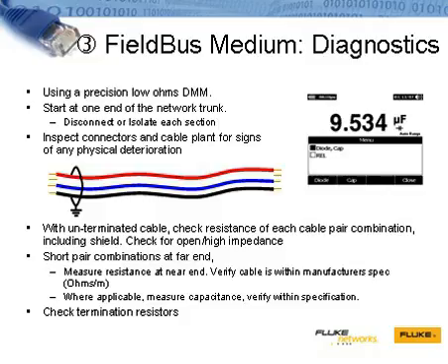Often in industrial field buses, we use standard common electrical AWG grade 2, 4, or 8 pair cables. These are untwisted or twisted cables with no set of special measurement standards yet defined. Unfortunately, to date, the industry has yet to define a common standard. Therefore, at a minimum, we must use a digital multimeter to test the basic characteristics like resistance and capacitance.